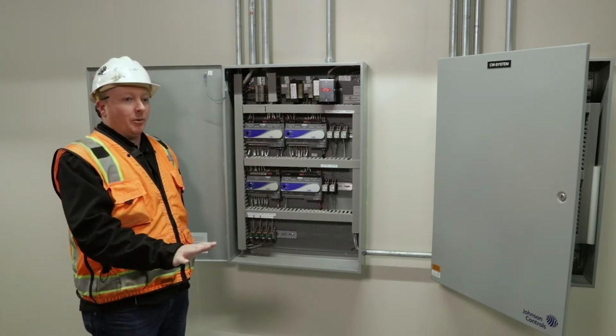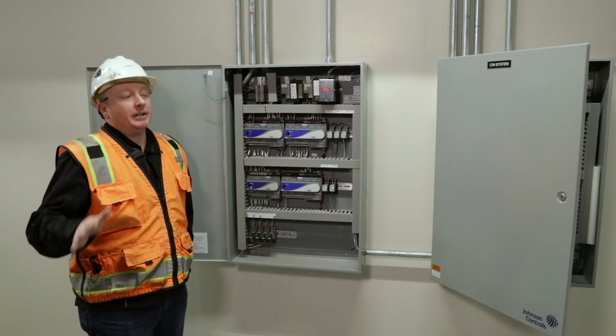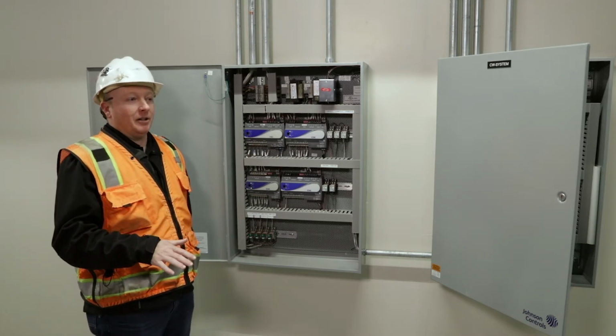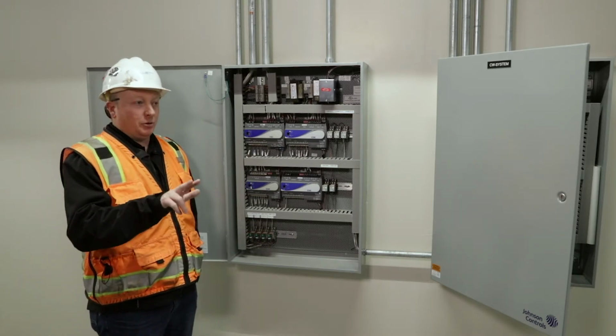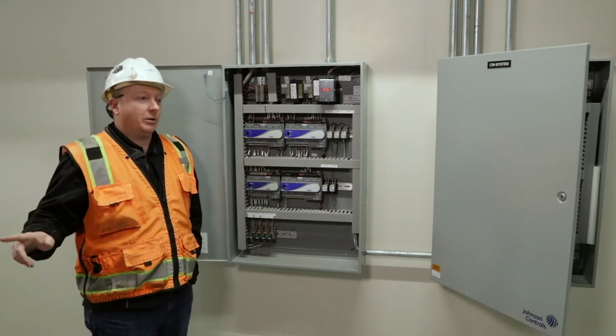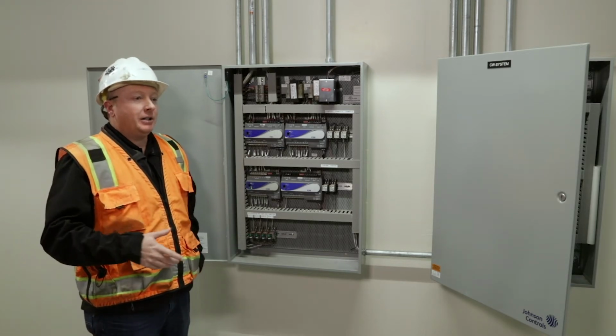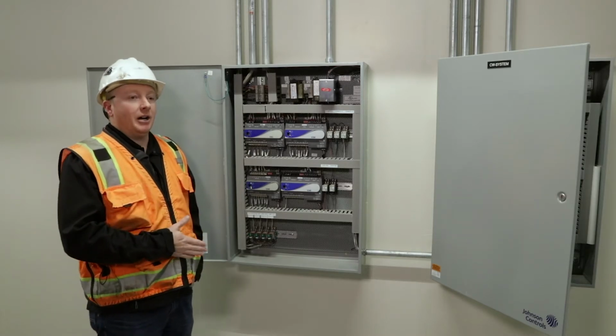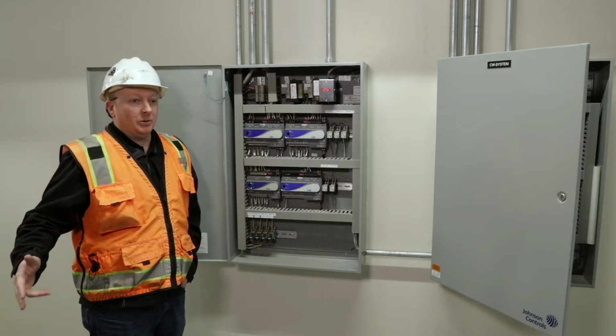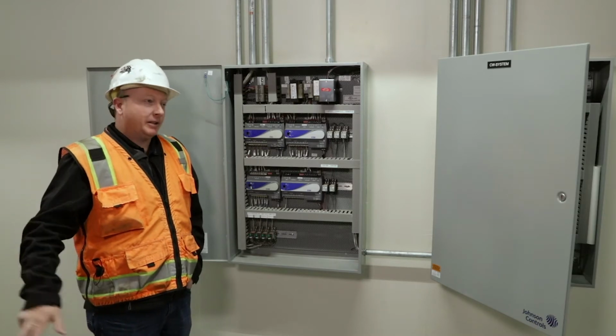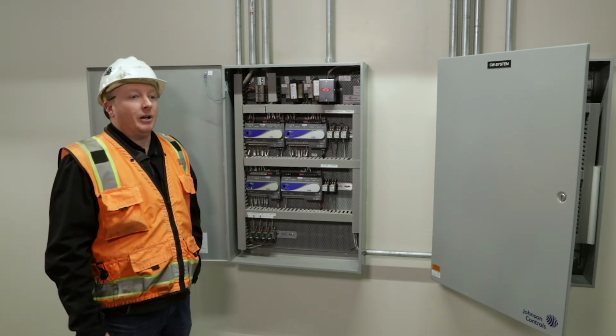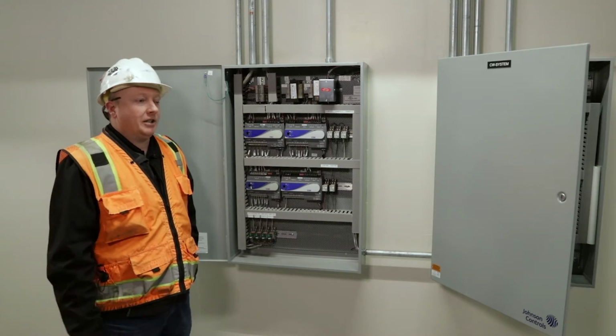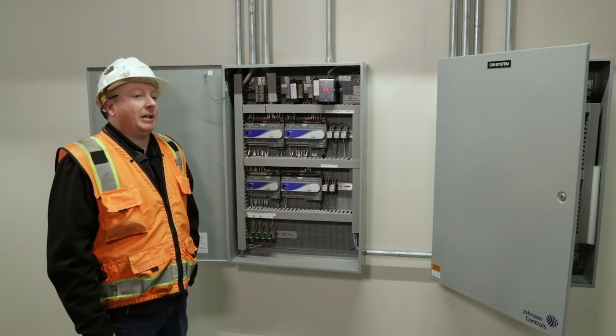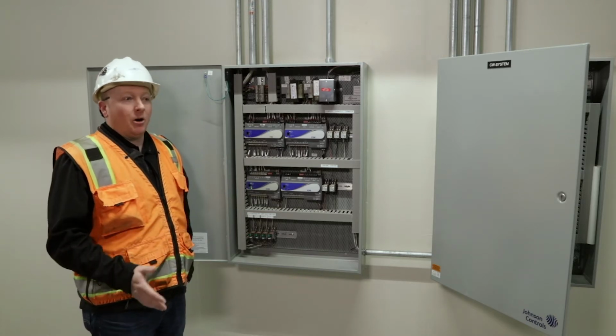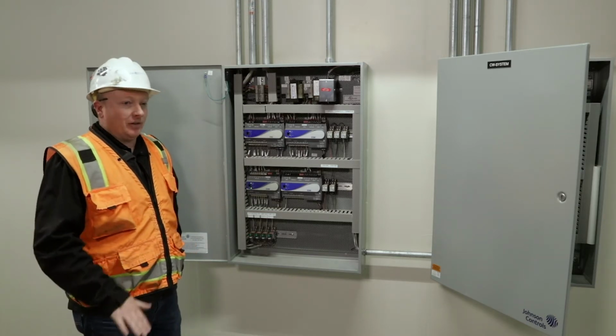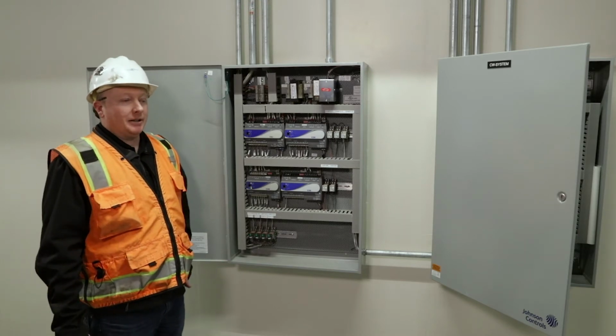We have a tower running, everything's happy. The towers actually stage based on temperature, so we can have 2 tower cells open with only 1 chiller running if we need to. So the towers stage independently of the chillers. If we do get into a situation with both chillers running, then we just force both towers on, and there's no more staging. They just ramp the fans to maintain set point. The fans will ramp together always. If we have 2 towers running, those fans will be ramping together, always running at the same speed.